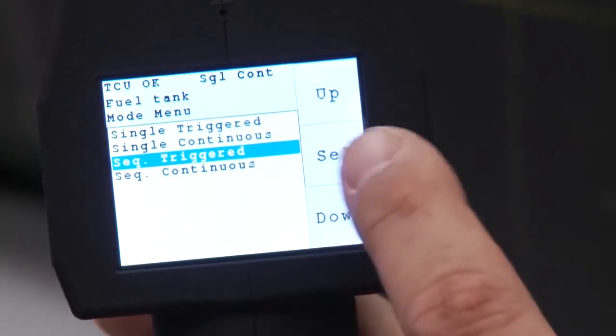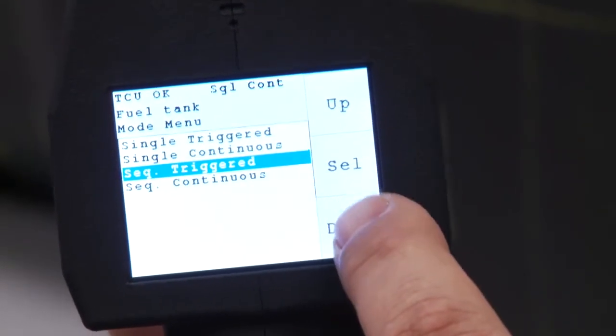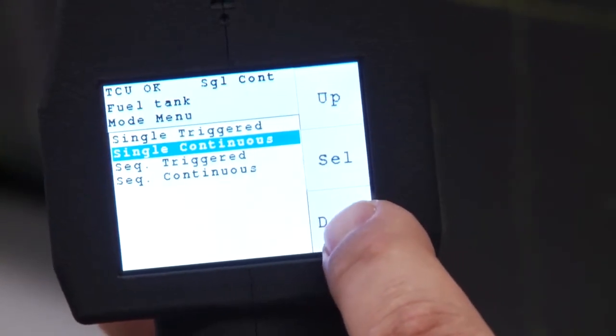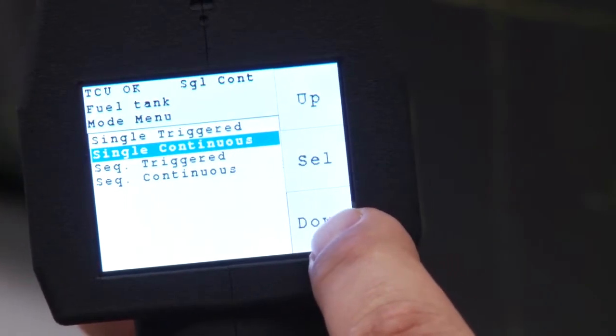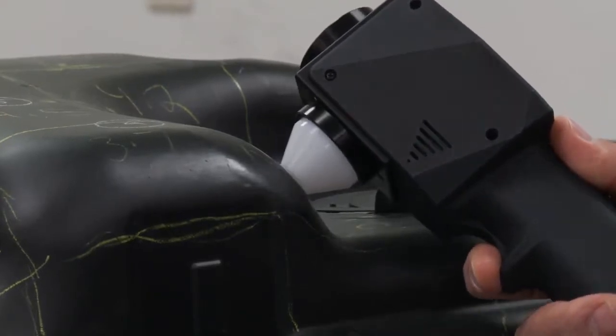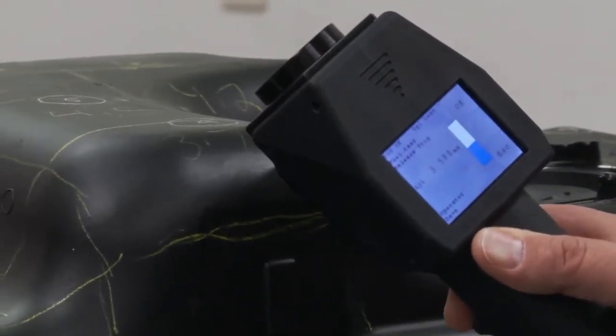A second mode, continuous, allows the operator to view the measurement over a period of time. This allows scanning of an area to see how the thickness changes with position.